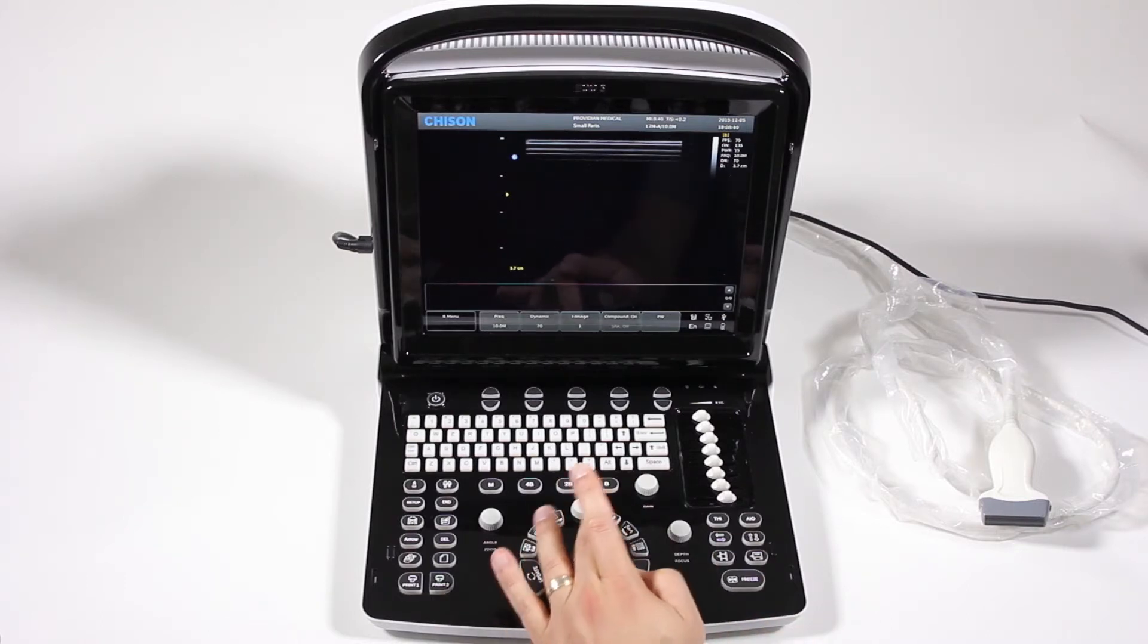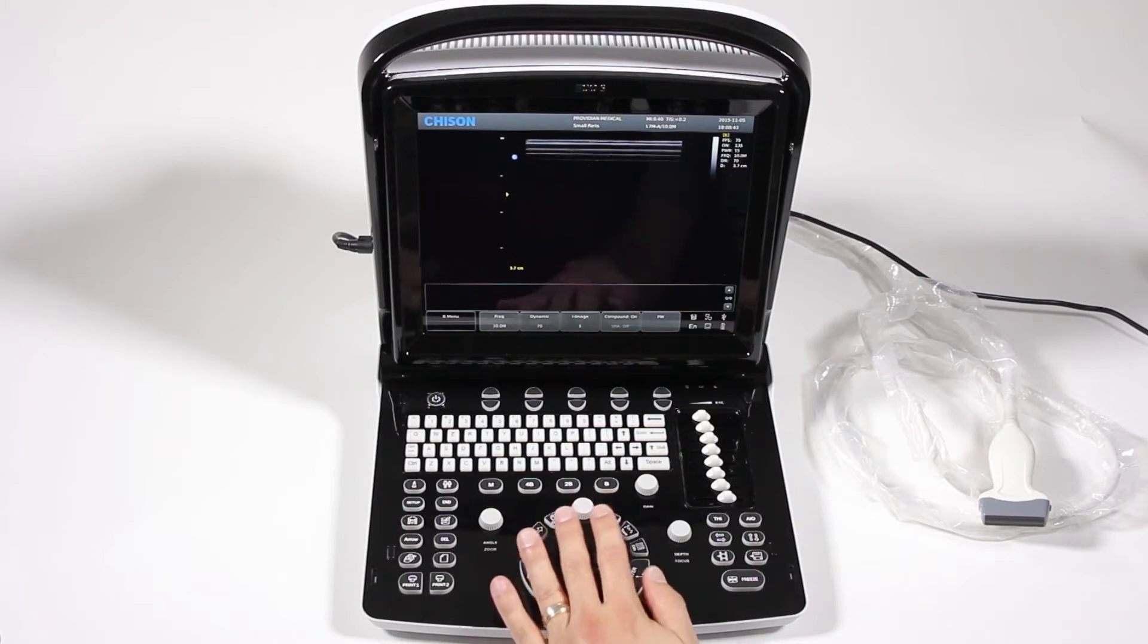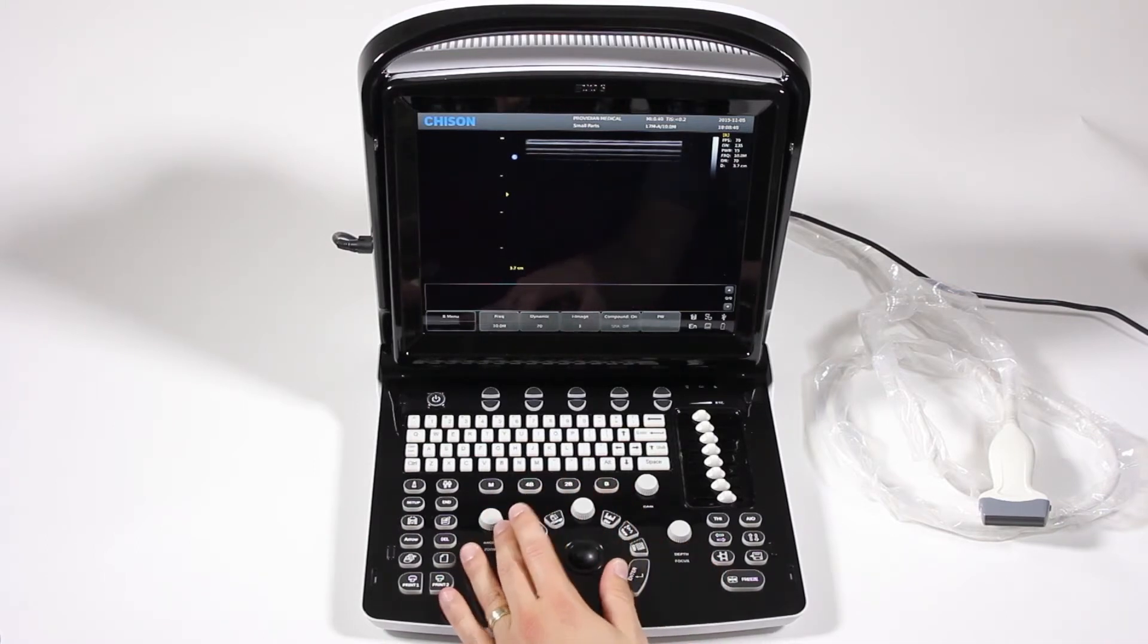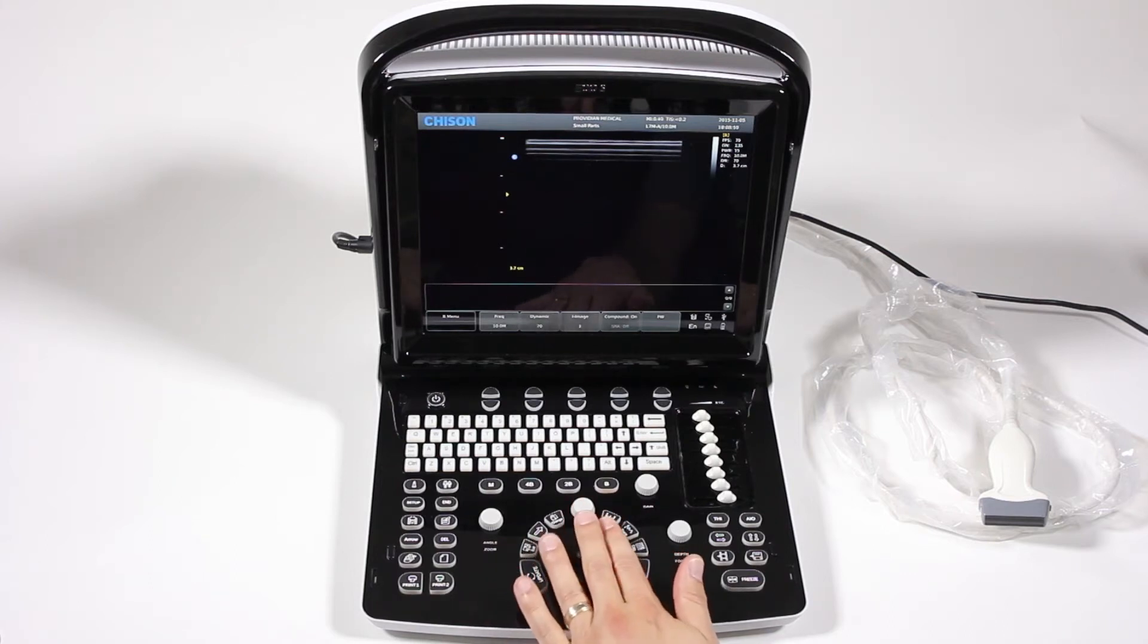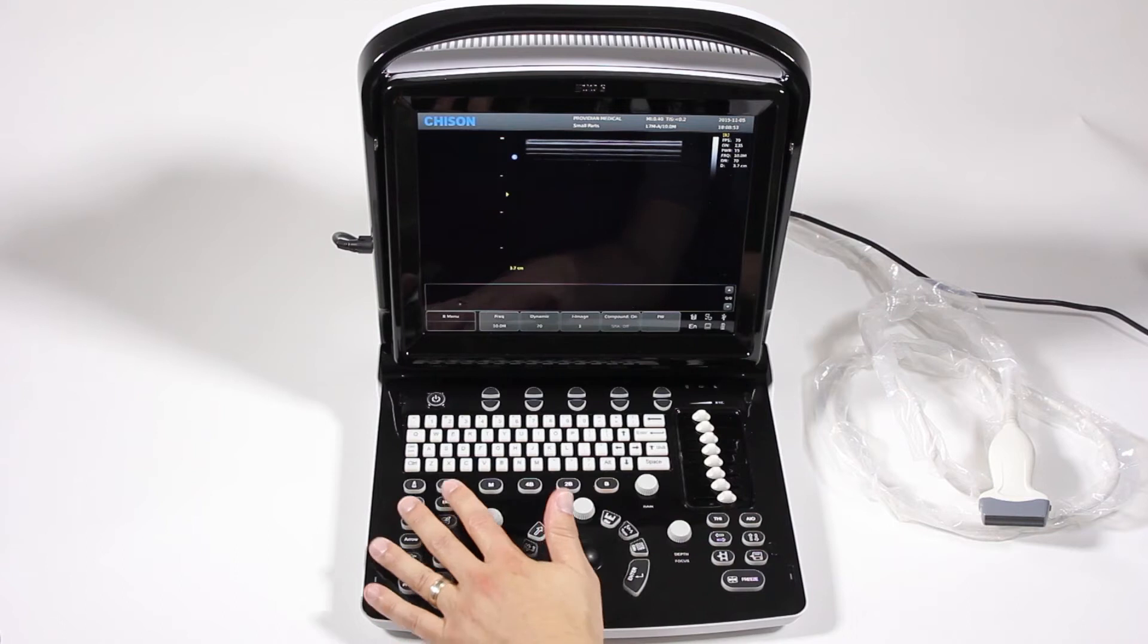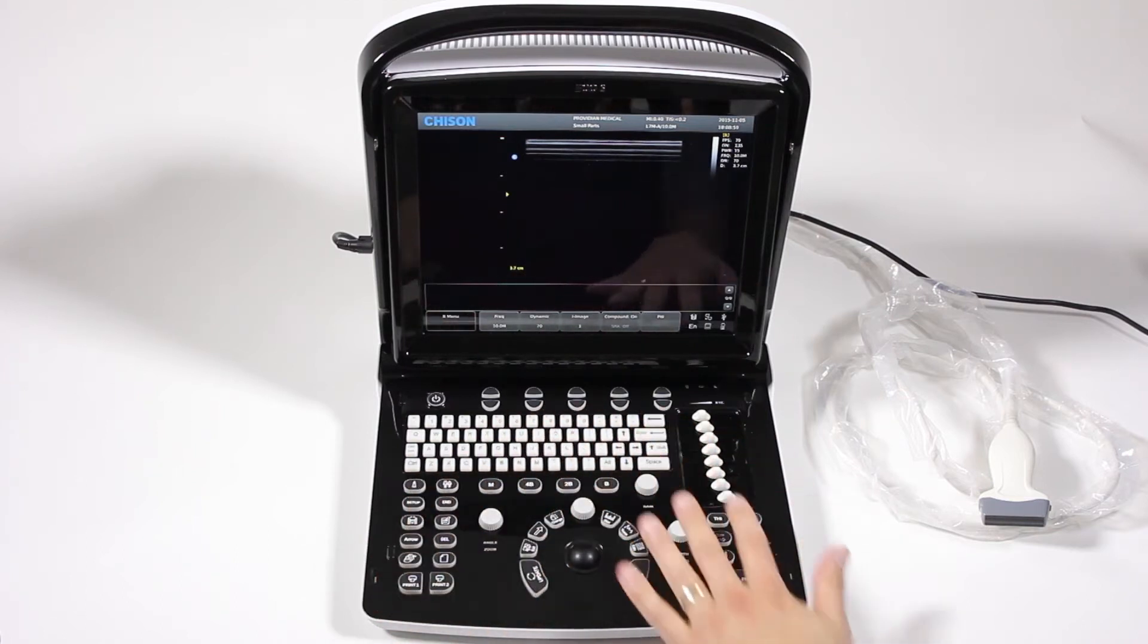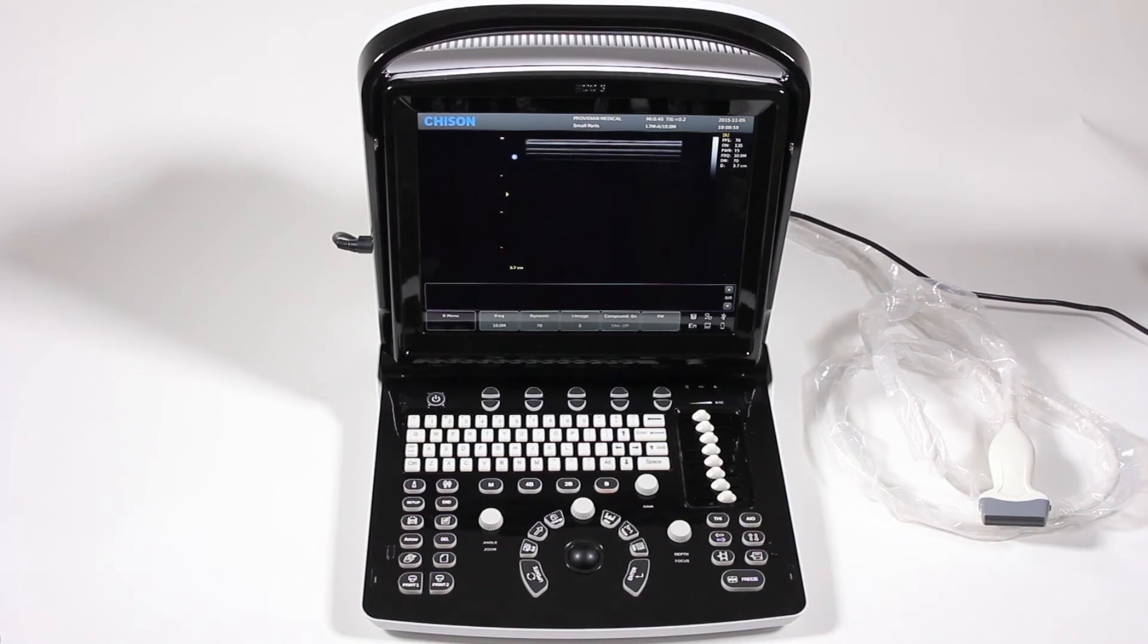First, let's look at the design. The machine is designed around your hand. This is called a home base design, where the things while you're scanning are going to be closest to where your hand will be positioned over a trackball. Things that you'll do less during scanning would be over to the right or further away, things that you might only change every now and then during an exam, if at all.